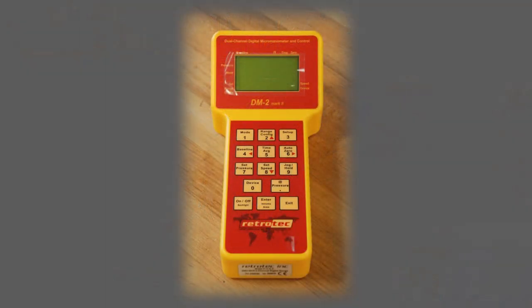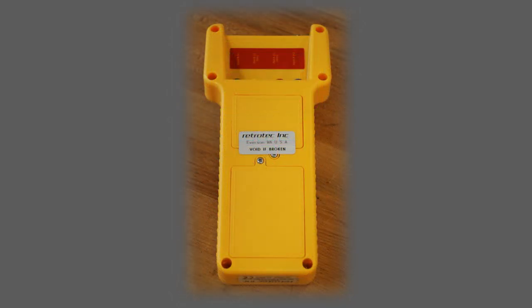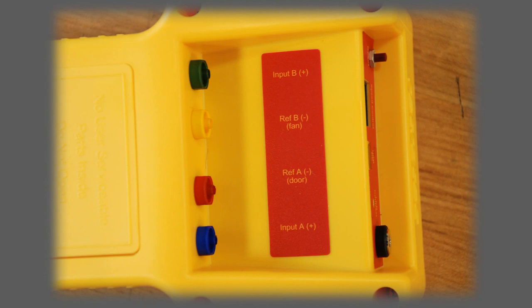All right, let's switch over to the Retrotec. So on the Retrotec, where are the port connections? In the back, right? Input on B. Okay, so that's your door. Reference on channel A. In this case, theirs is typically a red hose, but reference is going to go where? Outside. And the input on channel A was open. So this is channel A. The yellow and green are channel B. And if you notice right there, what does that say in parentheses? That goes to the fan, right? So it's similar. They both have two pressure channels, and then they'll read on the gauge here.